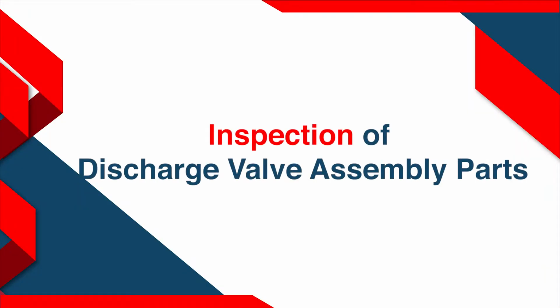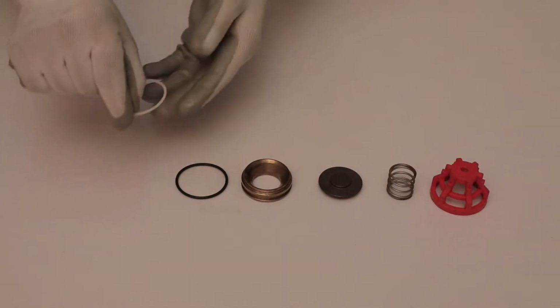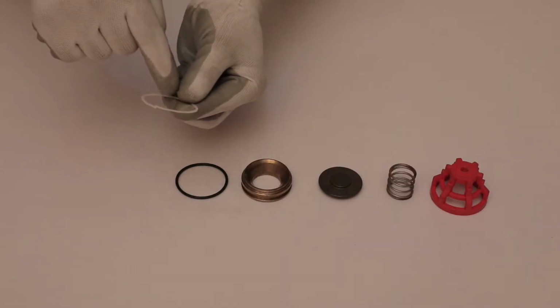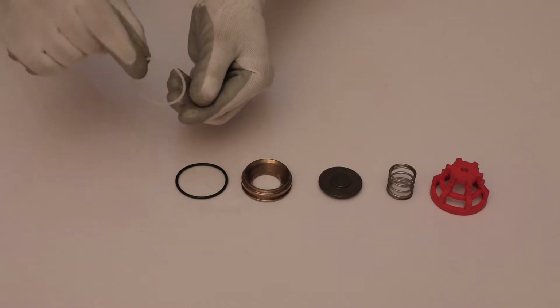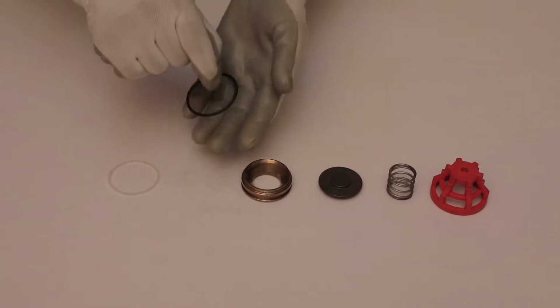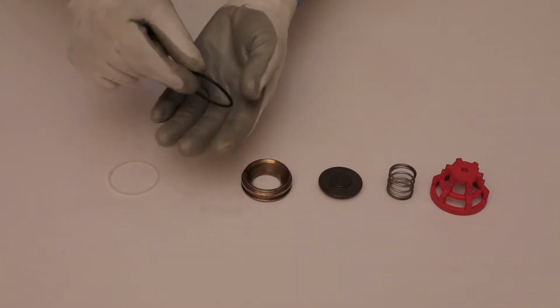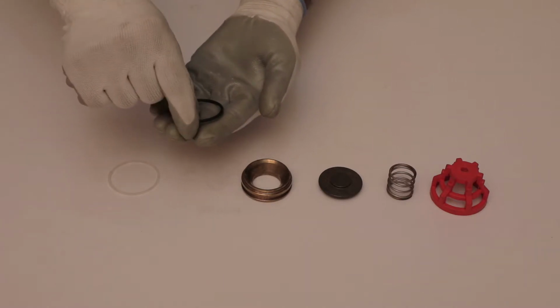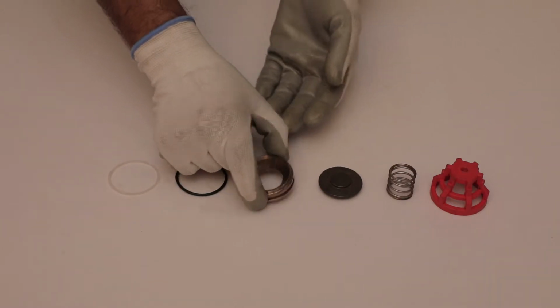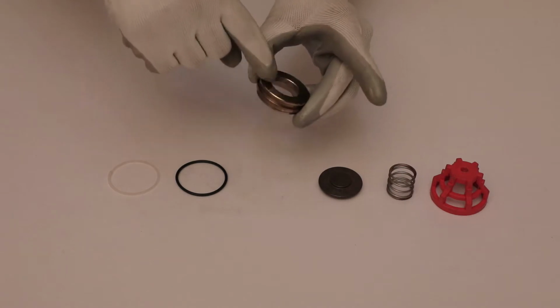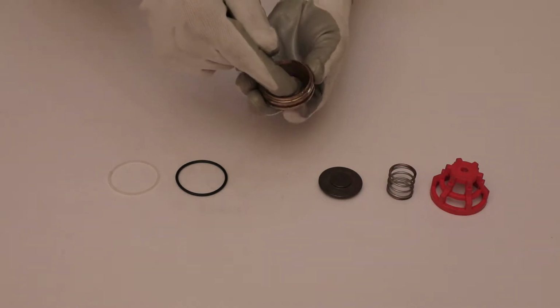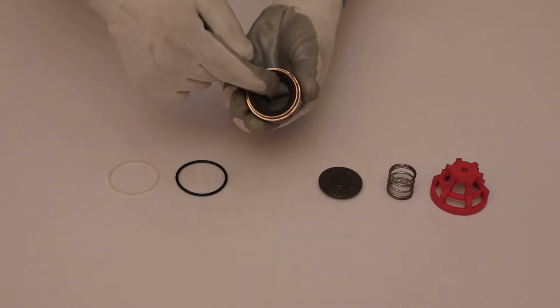Inspection of discharge valve assembly parts. Check the back ring for valve seat for any damage. Check O-ring for any damage. Inspect the surface of the suction and discharge valve seat for any wear or dent marks.